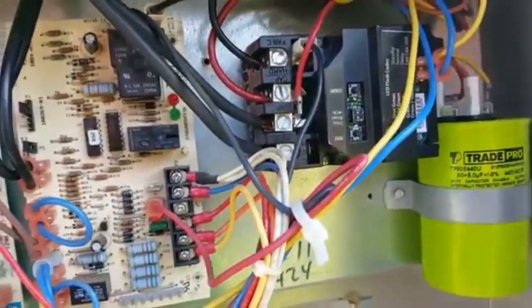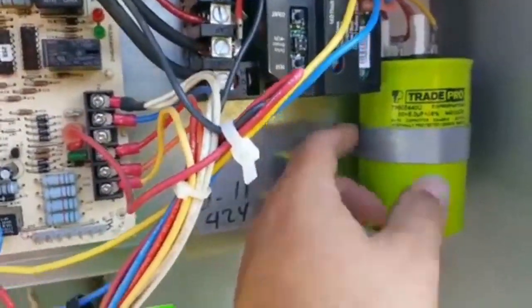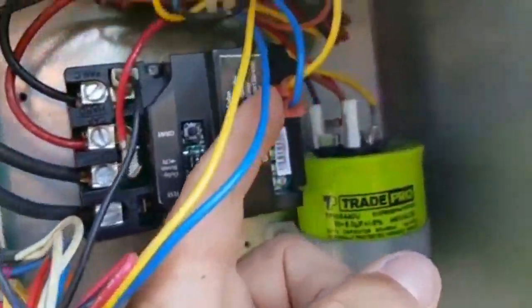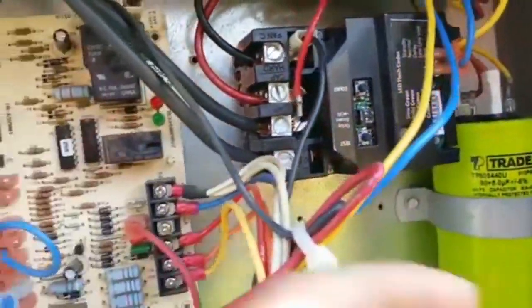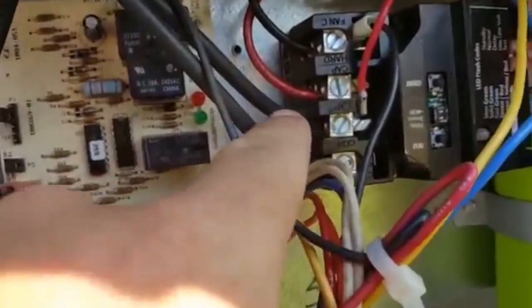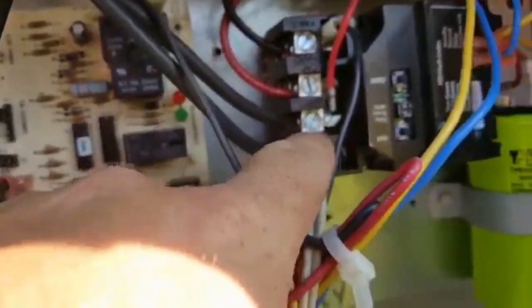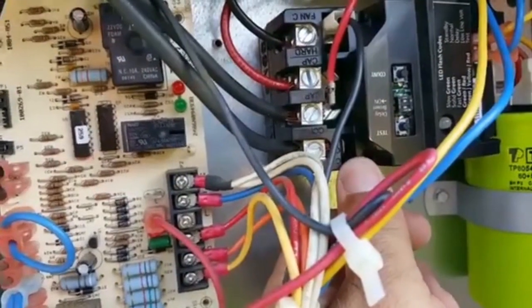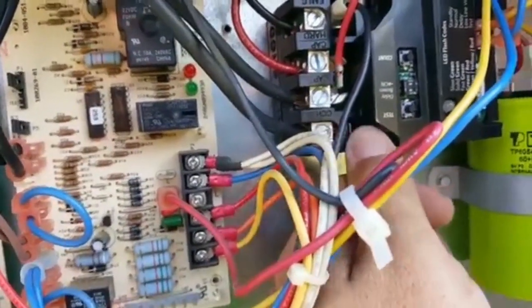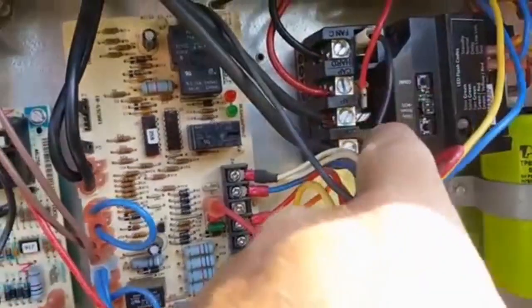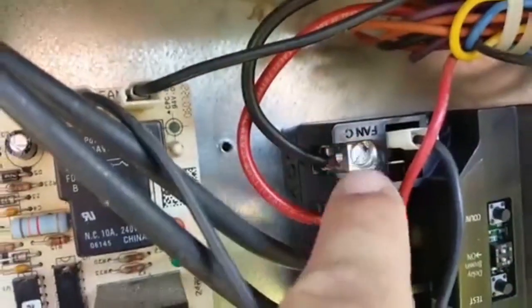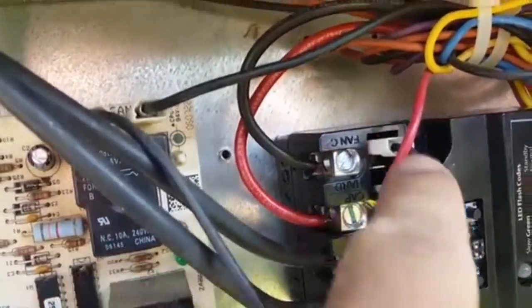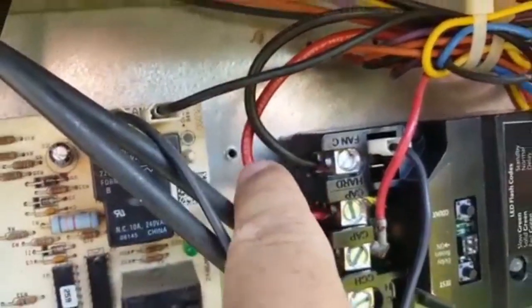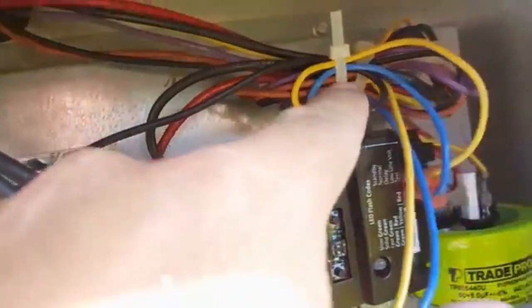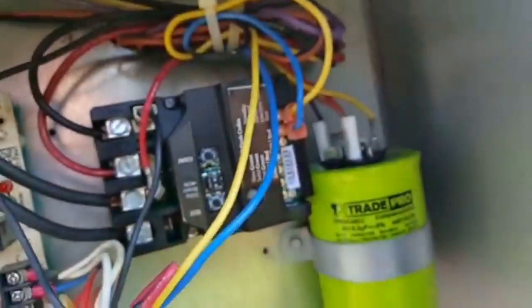I have my contactor in place, SureSwitch, new capacitor, have our low voltage up here, our wire 1 in common. We have our line coming in right here on these two lugs. Nothing on the crankcase heater. There's no crankcase heater for this unit. And of course that would be on the common is where that's heading. There's a switch here to the top side where we have our fan common, compressor common. There's the fan common, compressor common wire. It's the run winding wire, and we have the jumper over to the capacitor on the capacitor common.